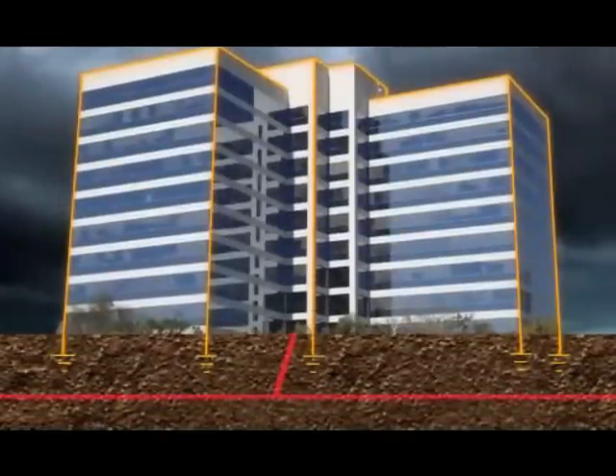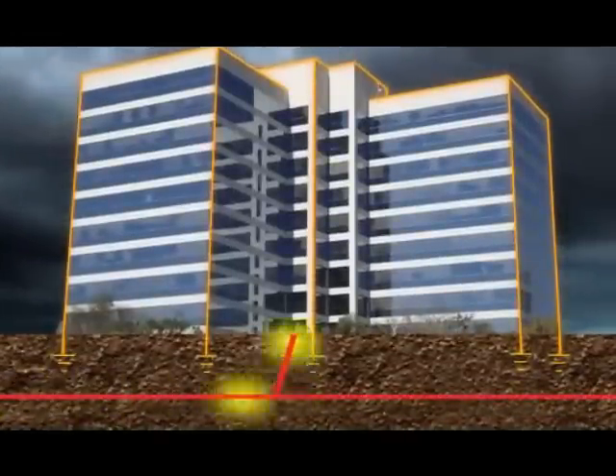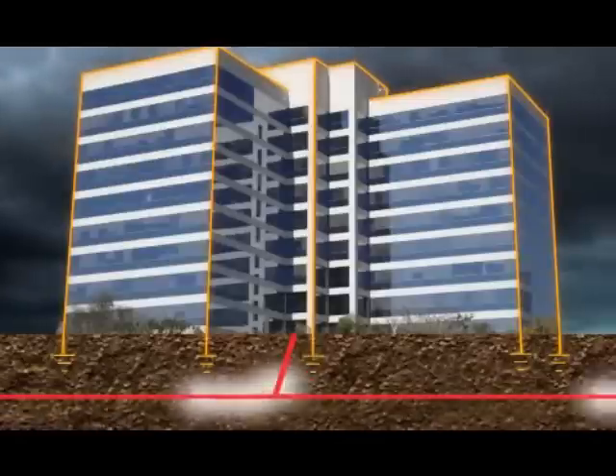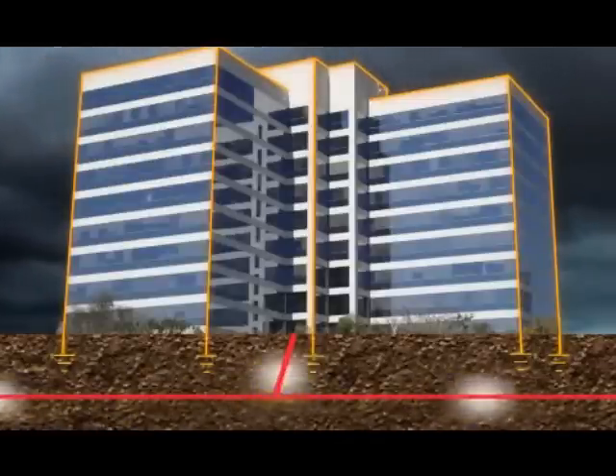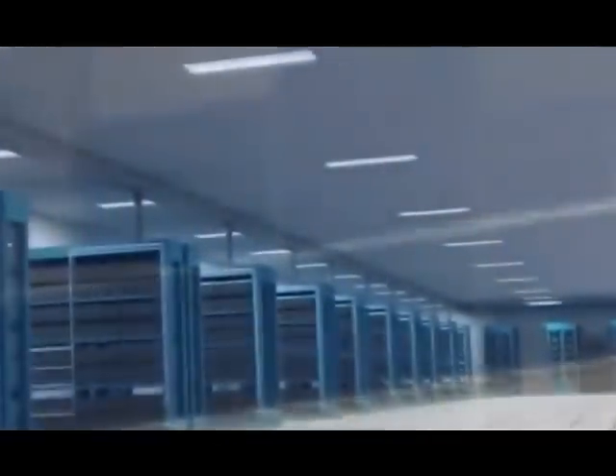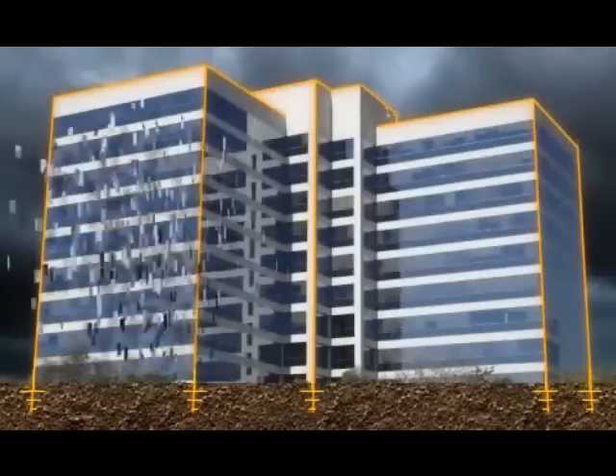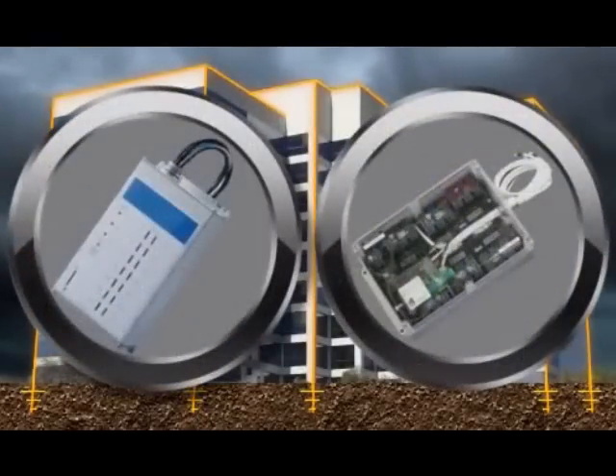Direct strikes are not the only dangerous threat created by lightning. Surges created by distant lightning strikes destroy sensitive electronics and appliances. In order to protect equipment such as networking equipment, servers, computers, telephones, and other media, surge protection devices, or SPDs, must be installed at the main electrical panel, telephone, and other service entrances.